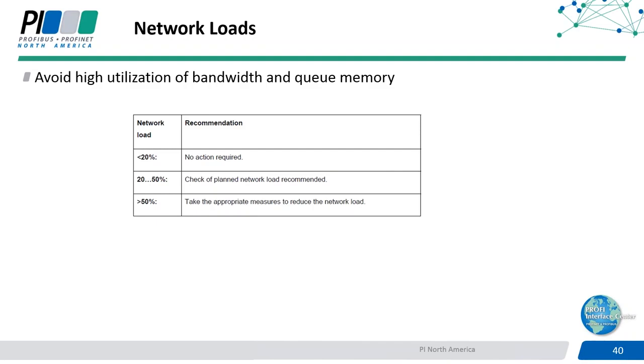Finally, we do not recommend going above 50% network load. If you have that, these higher loads may cause you to get dropped packets or resource issues and delays on your network components, through your switches or in your devices themselves, and we don't want delays out there in an automation system.